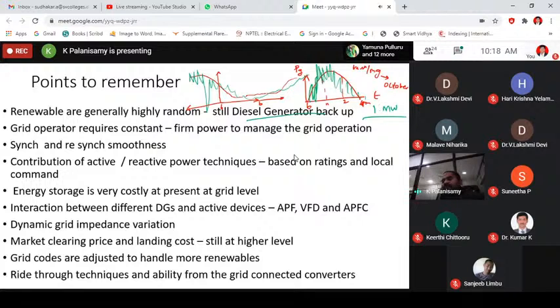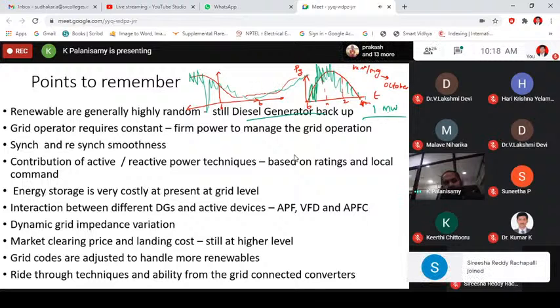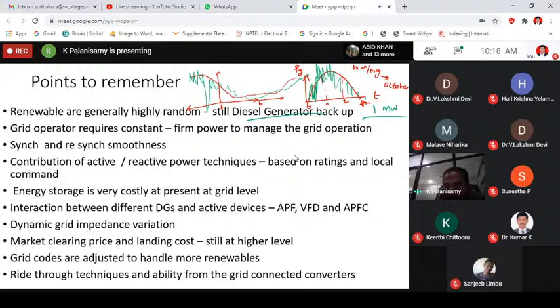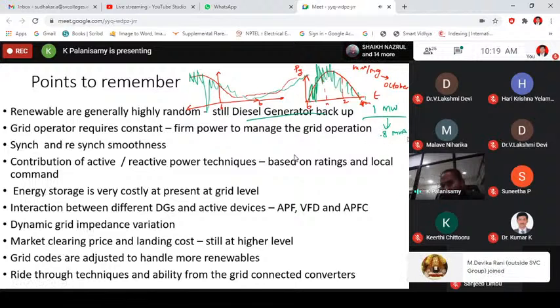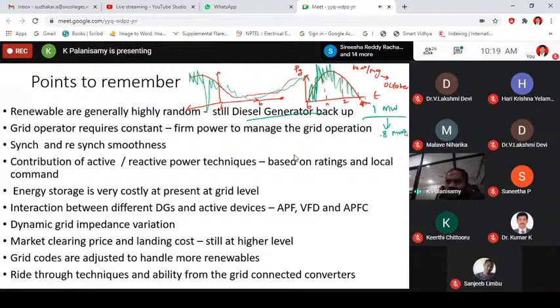Of course, you cannot have storage because that is very costly. Even if you plan it, it is a very optimized size. It cannot meet the entire power from solar and wind. That's very difficult. So you may need to run a diesel generator. If your load is 1 megawatt, the diesel generator backup, which I can call a hot or spinning reserve, will be at least 70%, maybe 0.8 MVA or 0.8 megawatt. So you have invested a lot in solar and wind or other renewables, but still, to meet the 1 megawatt load, a 0.8 MVA diesel generator is continuously running. It may not supply a good percentage of the load all the time; it may even go down to 10%.